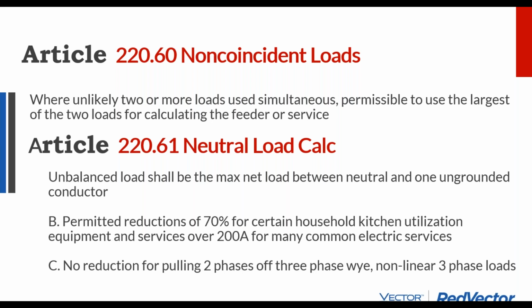Non-coincident loads: so electric code is saying, well, look, if these loads are going to be on at different times, it's possible to use the largest load of the two. For air conditioning loads, they'll look at running your AC to the maximum, running your heater to the maximum, or running a combination of air conditioning and heat to see what the maximum load condition is.